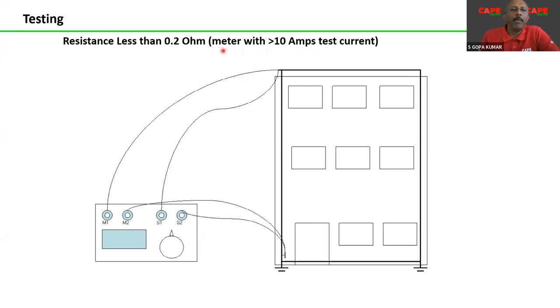The minimum requirement is that the meter used for this testing shall have a test current of minimum 10 amps. Anything higher than 10 amps test current is necessary, and the resistance from top to bottom shall be lesser than 0.2 ohms, 200 milliohm. So this is how the performance is ensured.